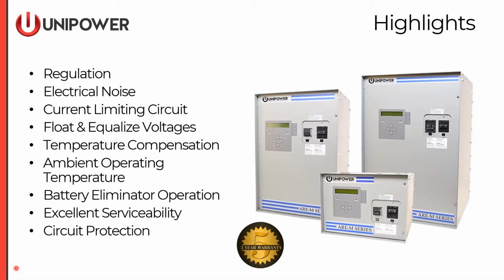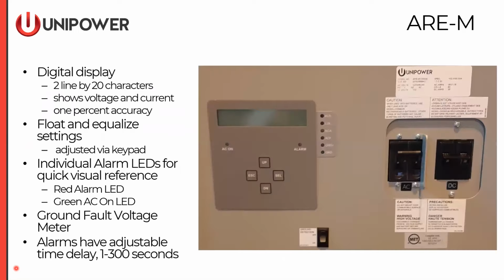We measure ambient temperature and compare that against the battery temperature to alarm if there's anything out of balance. We also offer a battery eliminator option if you need to black start these units or run them without batteries. Excellent serviceability. Again, we're going to show you the inside. Very easy to service. All the serviceable parts are right inside the front cover, and it does offer circuit protection, so the unit will protect itself in a failure mode. John Rambin, I'd like to turn it over to you to talk about some of the details of the specifications and serviceability of the ARE-M Ferro Resonant charger.